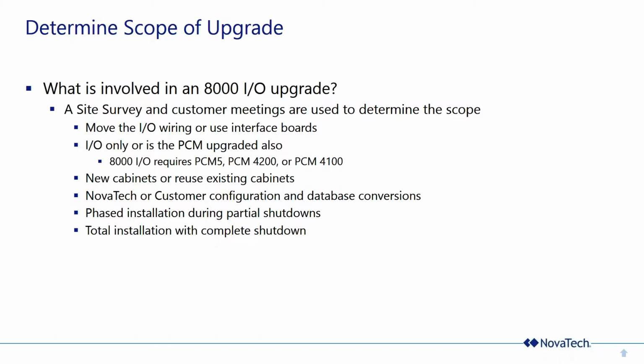To give an example, we've done complete upgrades. I personally was at one in Mexico where we did 33 I/O cabinets, over 2,700 I/O points, and also PCM upgrades and server upgrades. I mean, it was a complete upgrade from 1996 to 2015. In about 2 days, we had the first I/O cabinets turned back over to the plant, and they were starting to check out that I/O. In 7 days, all of the I/O was turned over to the plant. That is feasible. That can be done based on our experiences.